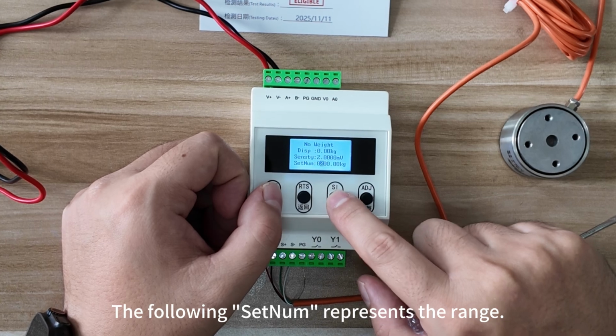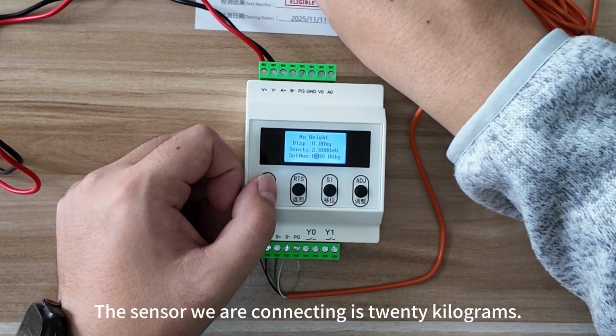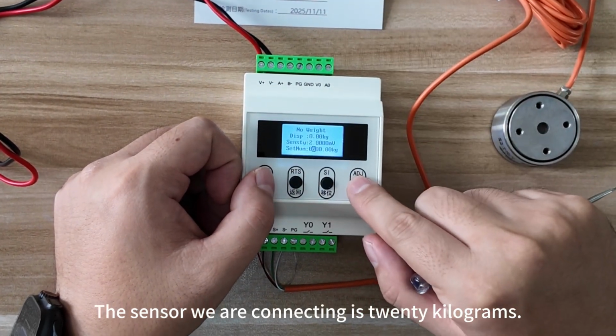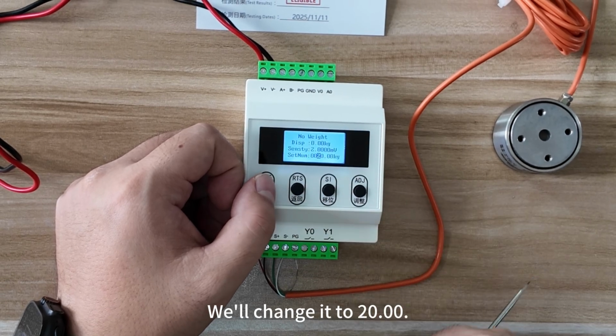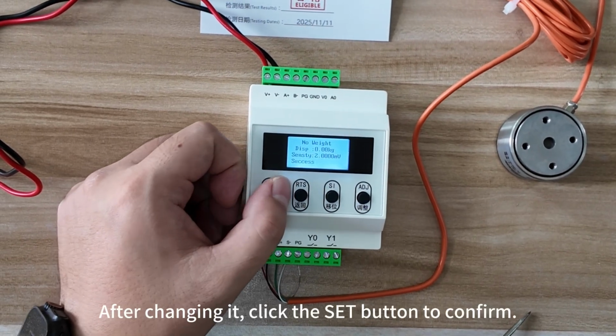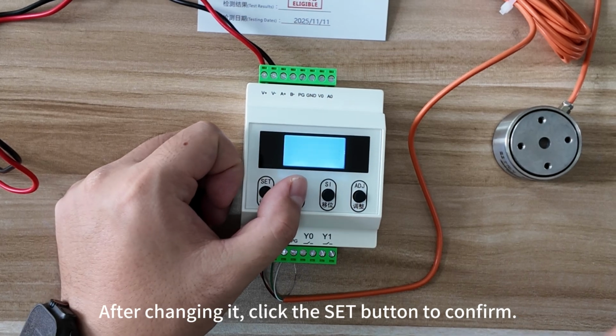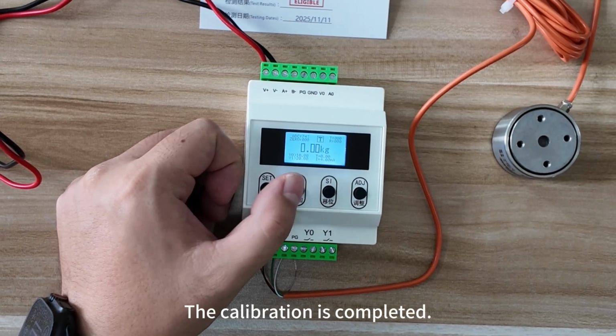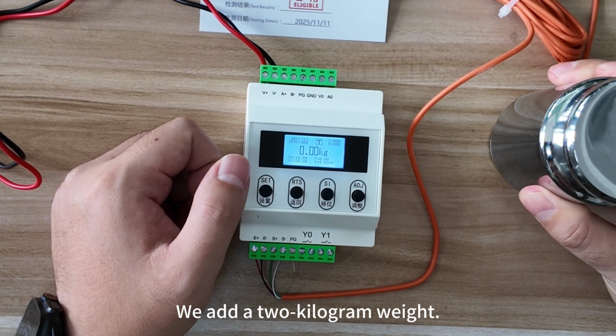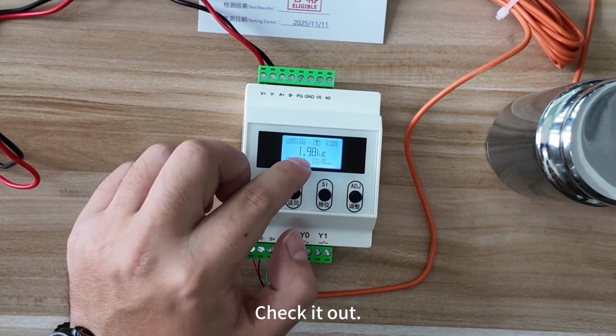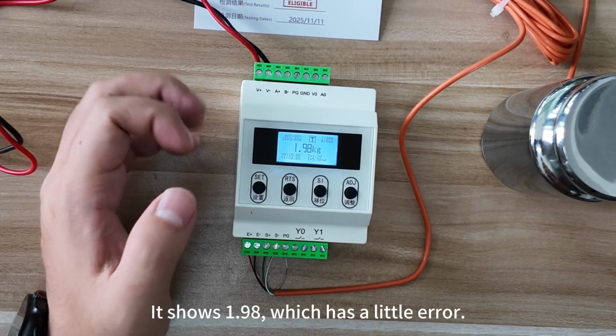The following setnum represents the range. The sensor we are connecting is 20 kilograms. We'll change it to 20.0. After changing it, click the SET button to confirm. The calibration is completed. We add a 2 kilogram weight. Check it out. It shows 1.98, which has a little error.